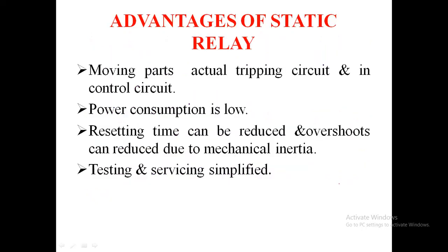Some of the advantages of static relay are: no moving parts in the actual tripping circuit, and in the control circuit power consumption is low, resetting time can be reduced, and overshoots can also be reduced due to the absence of mechanical inertia. Testing and servicing are simplified. So these are some of the static relays and the advantages of using a static relay.